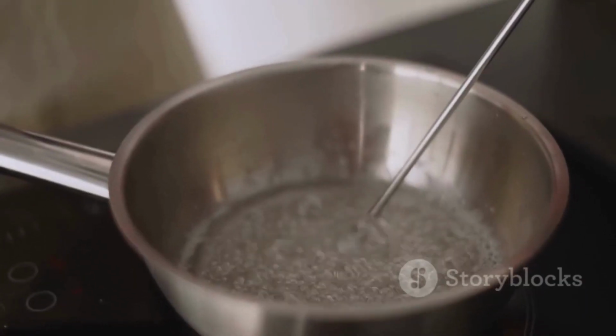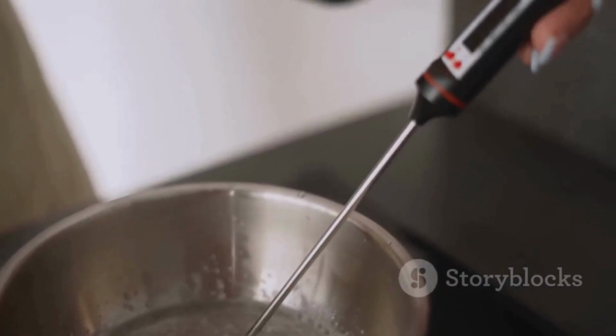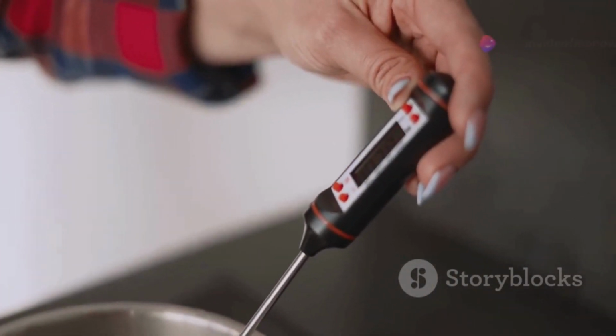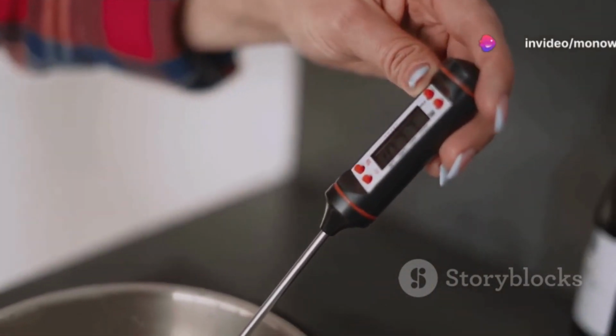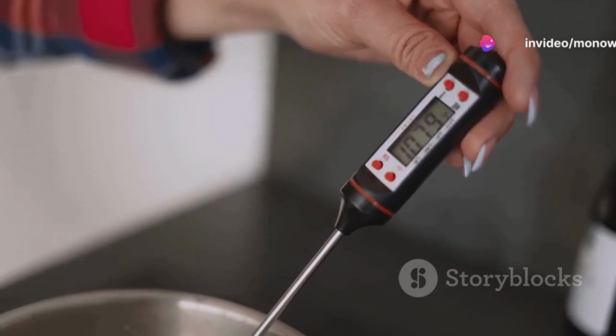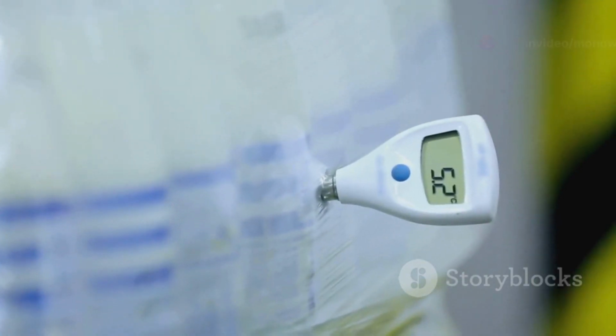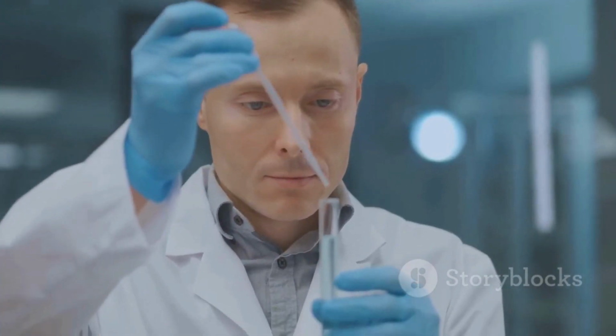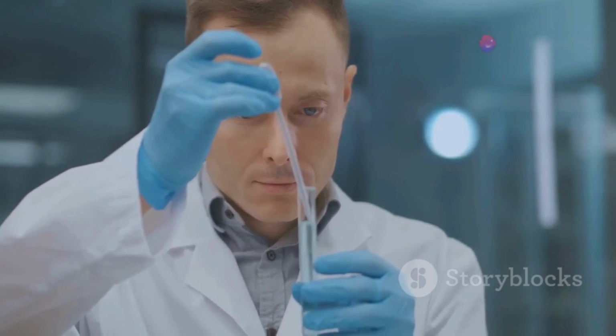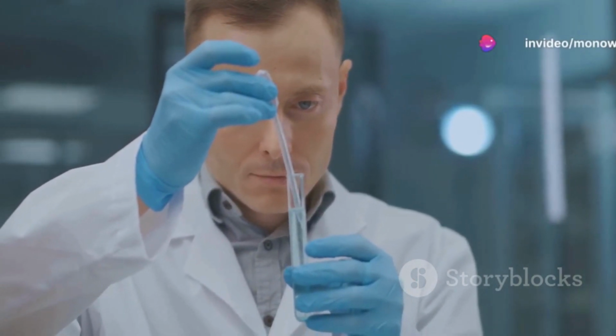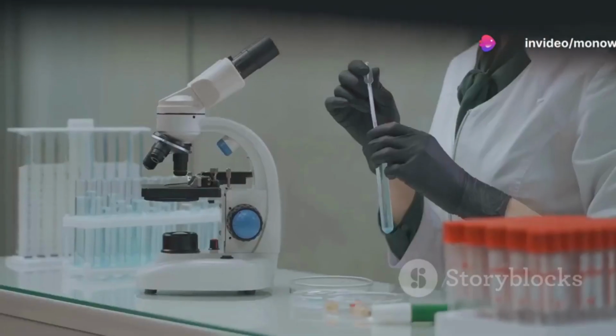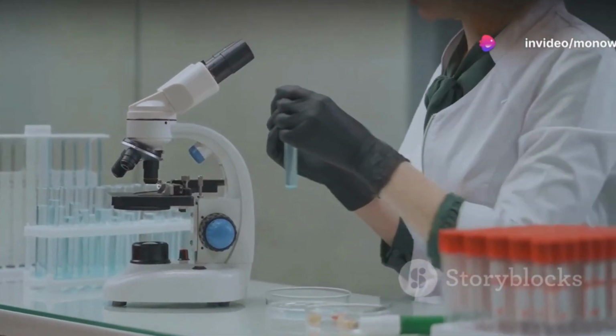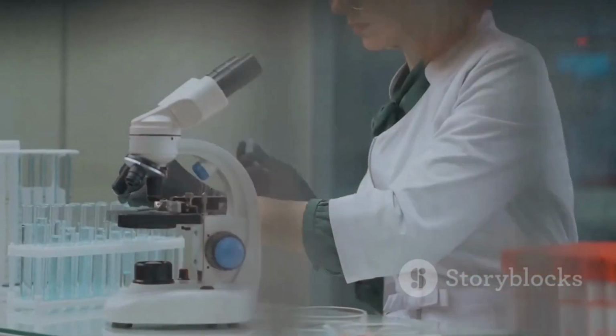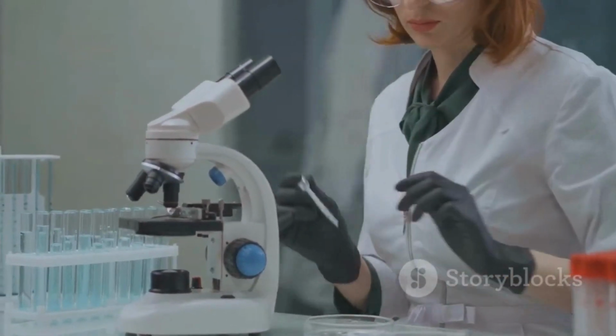You can manage these uncertainties in several ways. For instance, you can control the ambient conditions during calibration, handle your thermometer with care to minimize mechanical stress, and use calibration standards with known uncertainties. You can also invest in training for your calibration technicians to ensure they're up to date on the best practices and techniques. And of course, you can adopt quality control processes that regularly check for and address any sources of uncertainty.